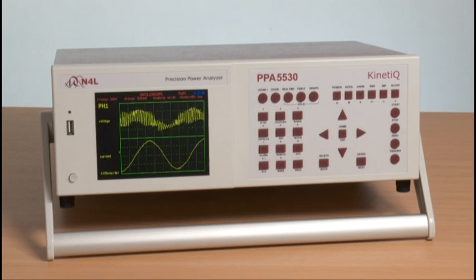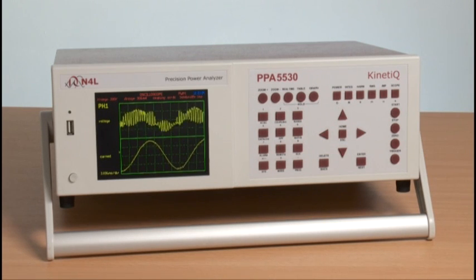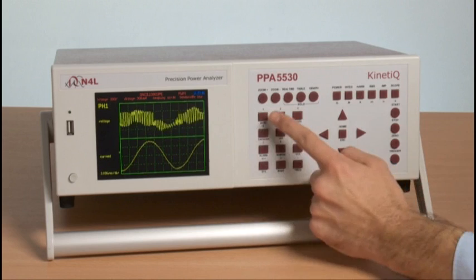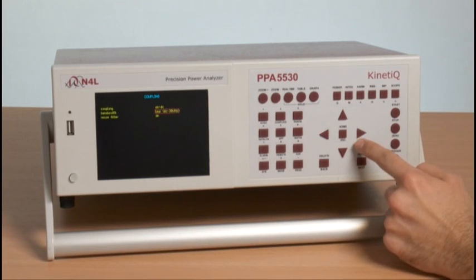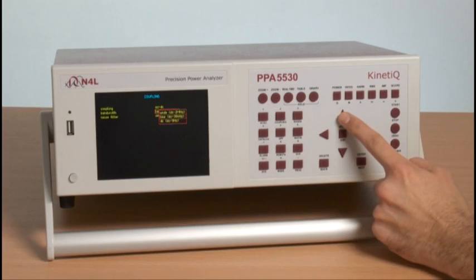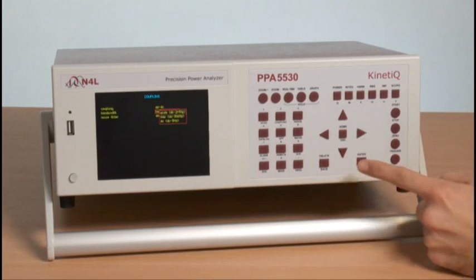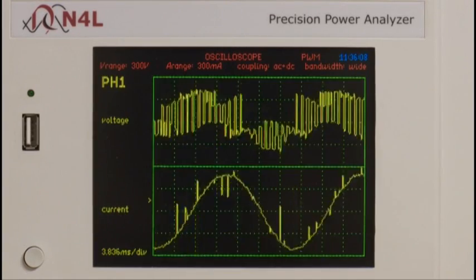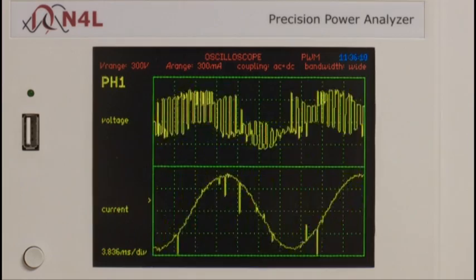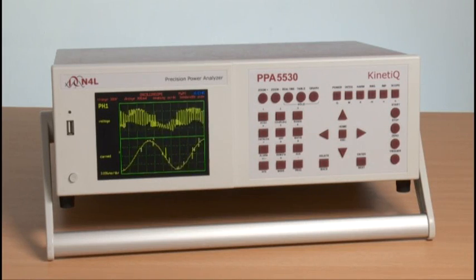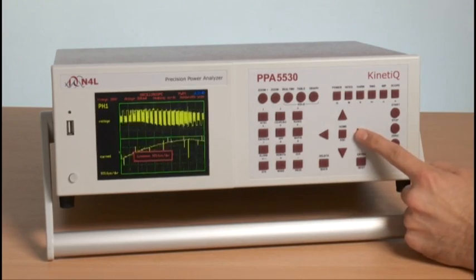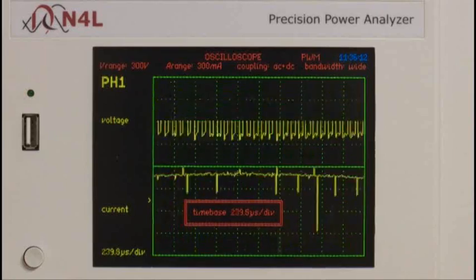However, the impact of this filtering on the voltage waveform is also significant, and we would like to illustrate this. First, we will return to a full 2 MHz bandwidth using the bandwidth function so that there is no filtering. We can clearly see high frequency noise visible on the current waveform again. Using the scope mode timebase control, we can zoom in to the voltage waveform in order to look at the PWM switching.